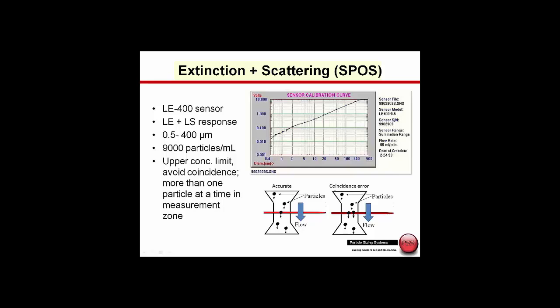This is the calibration curve for the combination light extinction and scattering sensor. This is for the LE400 sensor, which has a dynamic range of 0.5 to 400 microns. The upper concentration limit we can work at with this sensor is in the range of 9,000 particles per ml. The reason there is an upper concentration limit is we can only have one particle at a time passing through the measurement zone. Two particles passing through at the same time would be erroneously reported as one particle of a larger size.